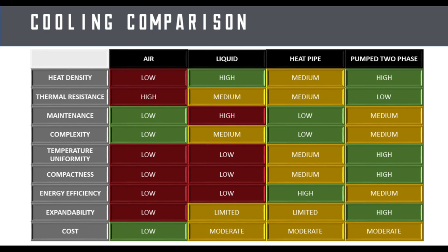Further comparing the cooling technologies, you can see a list of different metrics for the air cooling, liquid cooling, heat pipe solution, and a pump two-phase cooling solution. As you can see, the pump two-phase system provides the lowest thermal resistance while maintaining the tightest compactness of any solution available. Its cost is somewhere in the middle between all of the solutions, and it provides a high energy efficiency solution for any application.